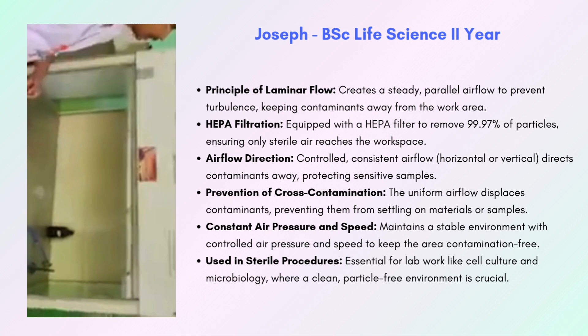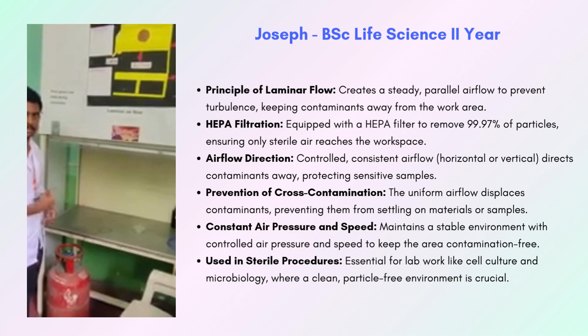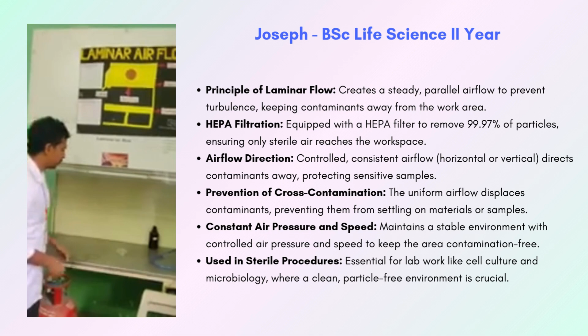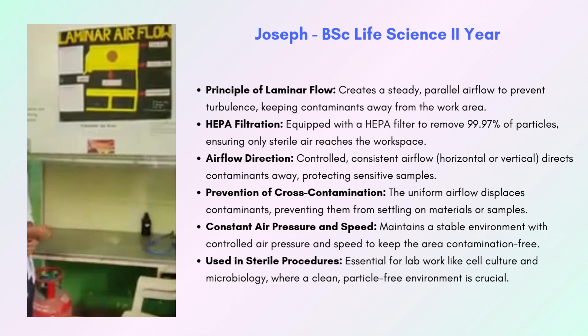Before using the laminar airflow cabinet, we have to disinfect it either with a disinfectant or using UV light. After that, before we begin the experiment, we have to switch on the HEPA air purifier for at least 15 to 30 minutes, so that every particle inside the cabinet comes out. When the air purifier is pumping out air, bacteria and dust particles cannot get in because it creates a positive air pressure inside. While working in a laminar airflow cabinet, always use sterile tools and petri dishes so that no contamination enters the culture medium through them. Thank you.